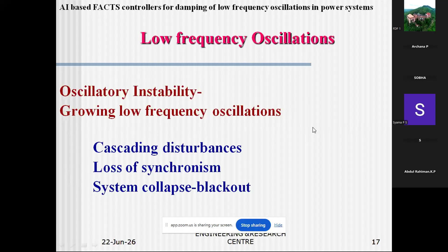So what is the method? What you are doing traditionally is adding power system stabilizers. Power system stabilizers means you are simply adding damping torque to the system. It acts on the machine excitation system and it is a proven technology for damping of local modes. So normally all systems are provided with PSS. So there will be enough damping torque in the total power system. There is no threat from the small disturbances which are happening, or the oscillations are damped out as soon as they are formed. So the system is stable.